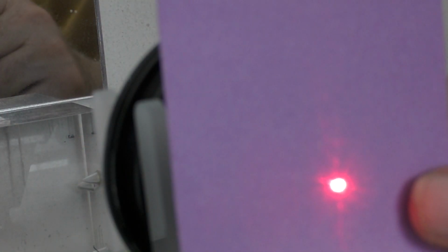We're not testing the spot size, we're testing what happens to that beam when it reflects back through the lens. There's the beam that's going into the lens. So if I had to put a circle around that dot, I would say it's probably about 4 millimeters diameter, which in essence is equivalent to the blue and the yellow zones on my Gaussian curve. So we've got basically a simulation of the high powered path there.